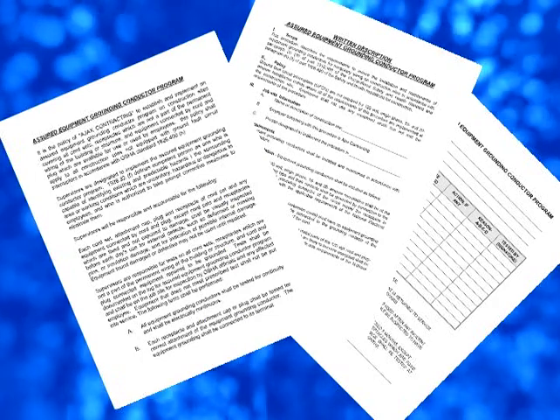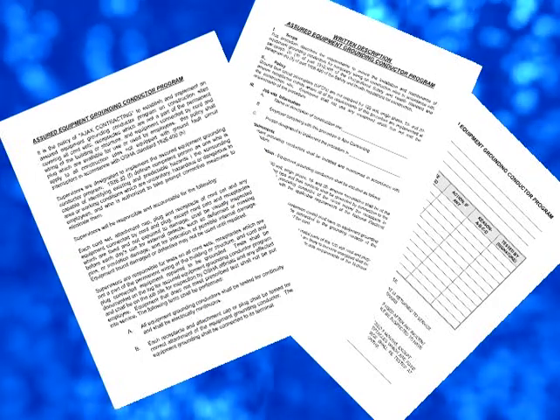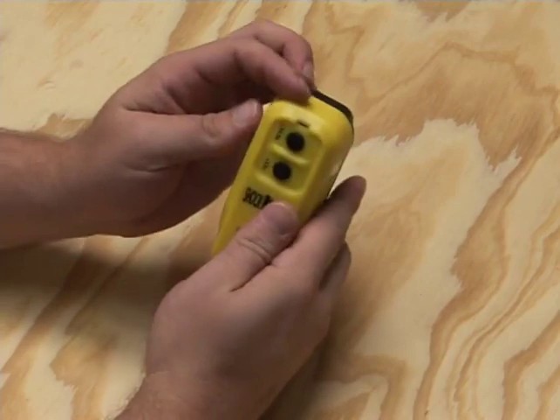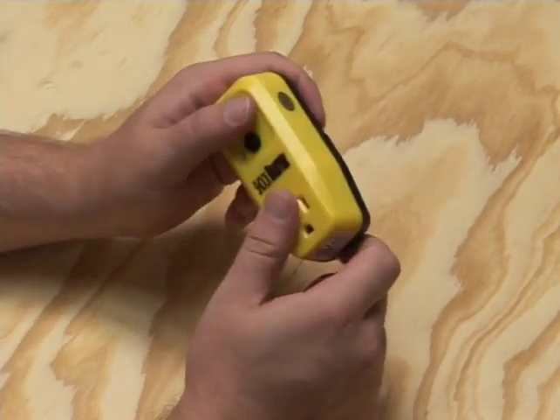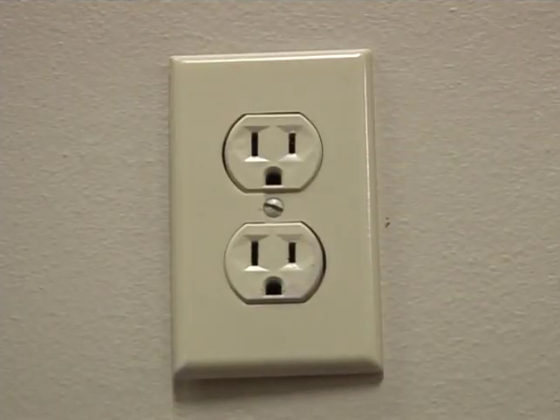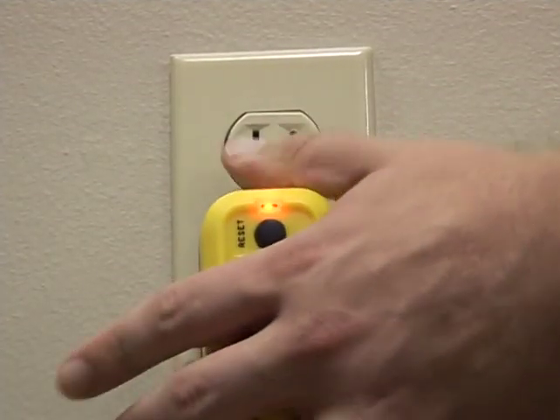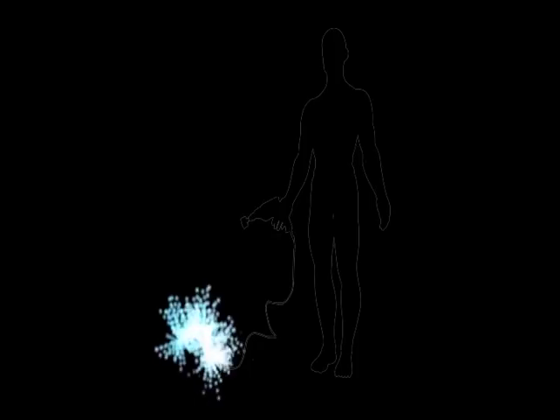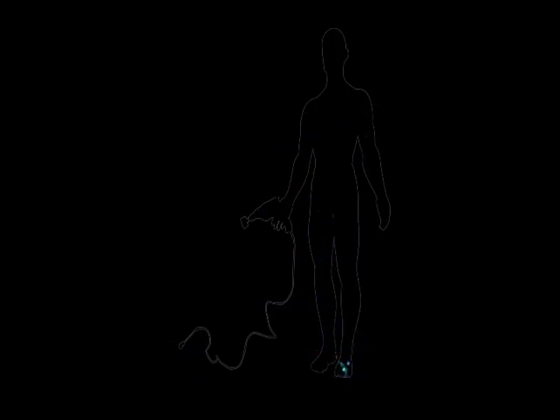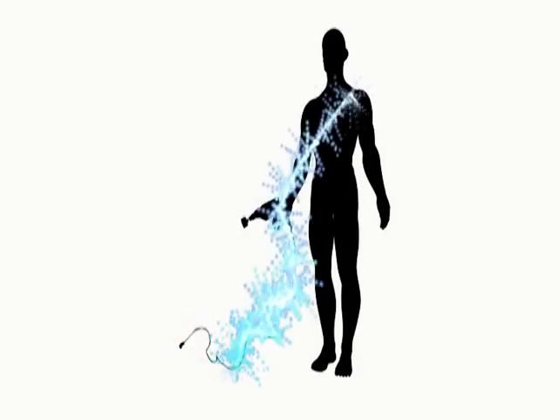OSHA also requires employers to provide either ground fault circuit interrupters, referred to as GFCIs, or a scheduled and recorded Assured Equipment Grounding Conductor program. A ground fault circuit interrupter is a fast-acting circuit breaker designed to shut off electric power in the event of a ground fault within as little as a 40th of a second to prevent electrocution. A ground fault is a break in the low-resistance grounding path from a tool or electrical system where the electrical current may take an alternate path to the ground through the user.